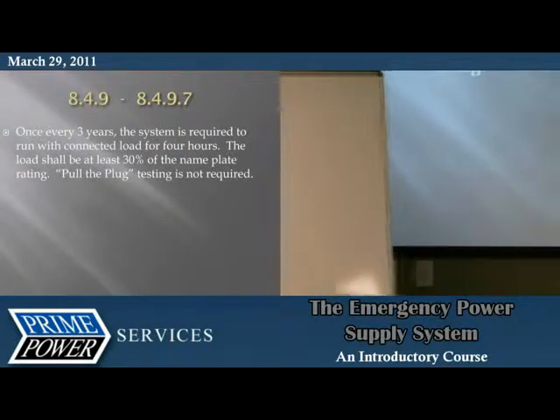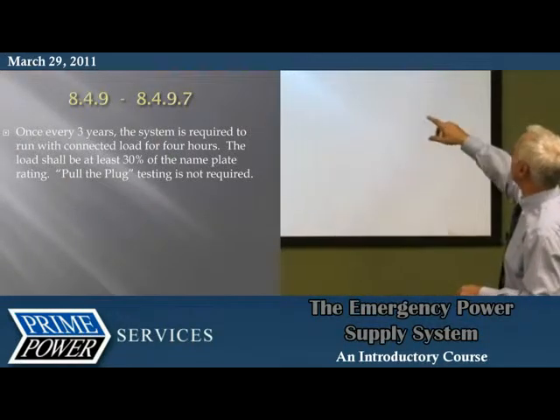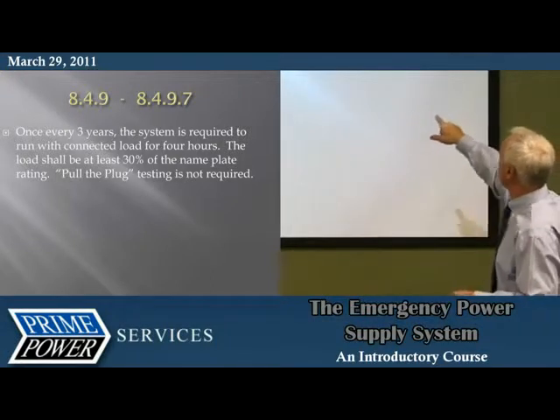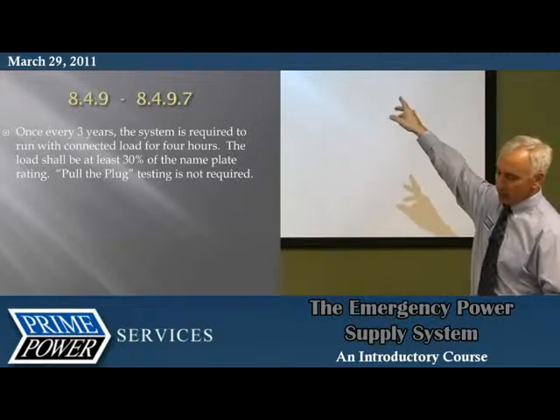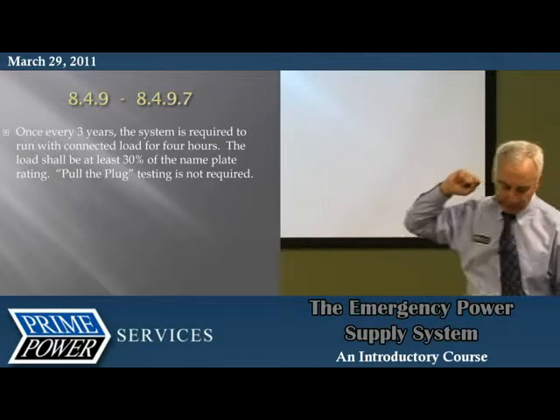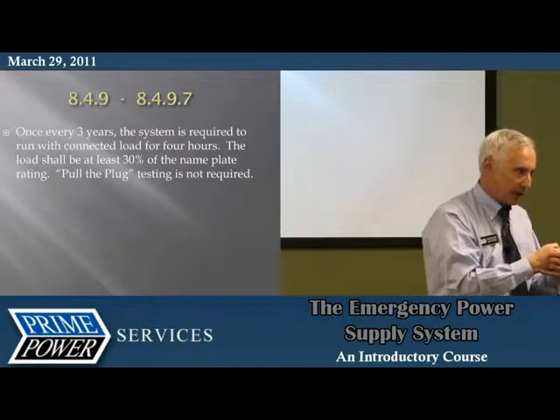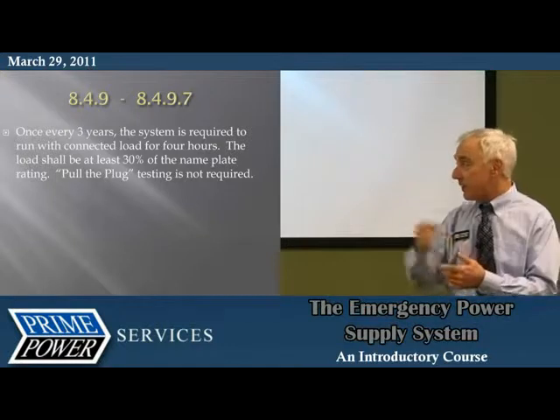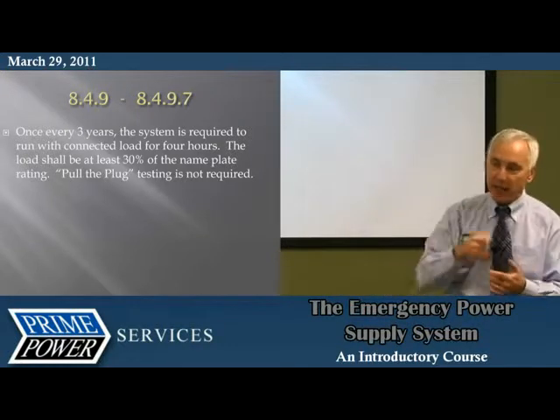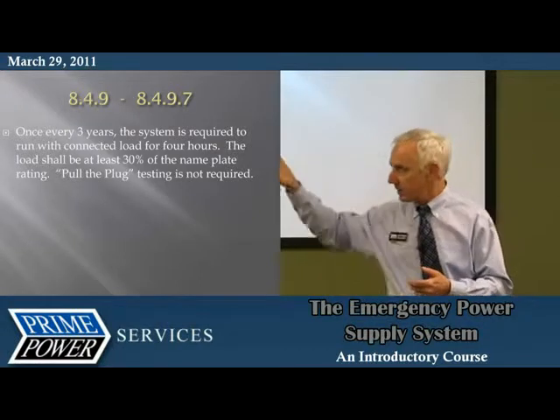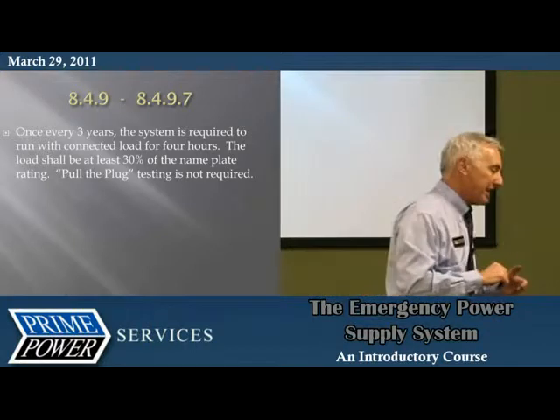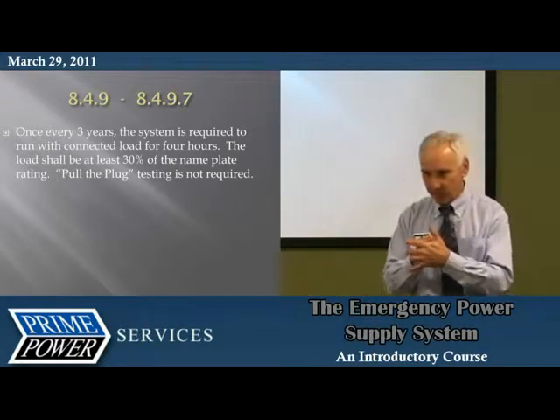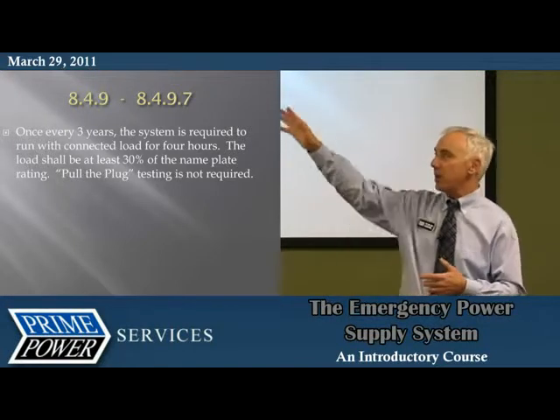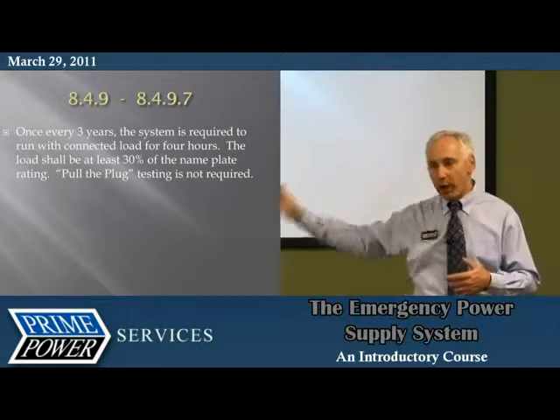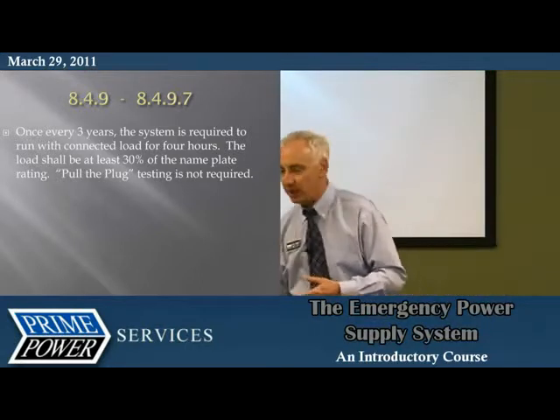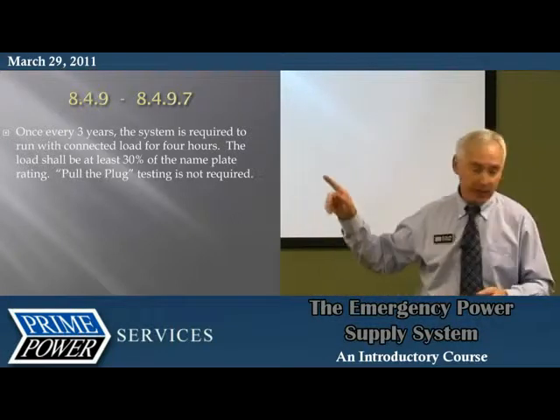So what NFPA tells us is that once every 3 years the system is required to run with a connected load for 4 hours, at least 30% of nameplate rating. Well, this is not the one I'm looking for, but this is still pertinent, because what they'll tell me is that 30% value means you need to load bank your generator if you don't see at least 30% load once a month. And that's for the health of the machine. If you don't reach that 30%, then we have to load bank it to burn this fuel off, to burn this system out and to clean out the system. So if you're intent upon running this 30 minutes, no load, then all you do is put more fuel out the exhaust, wipe your cylinders down more, and risk ruining this particular machine. Diesel has to have load for this particular reason.